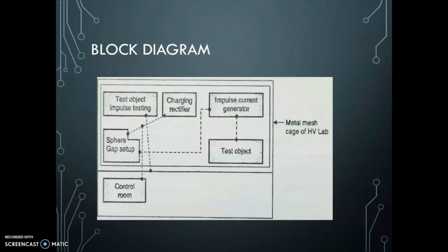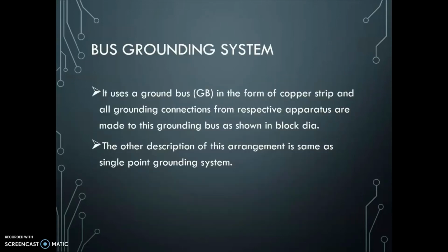Now the second one is the bus grounding system for the HV lab. In this system, the other descriptions of the arrangement shown in the previous one are the same, but the only difference is that it uses a ground bus in the form of a copper strip, and all the grounding connections from the respective apparatus are made to this grounding bus, as shown in the figure.